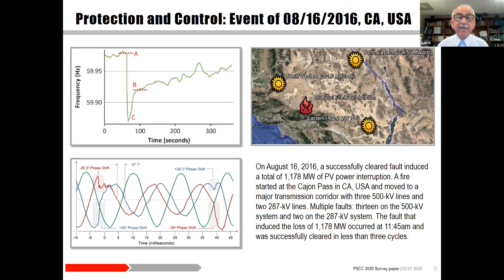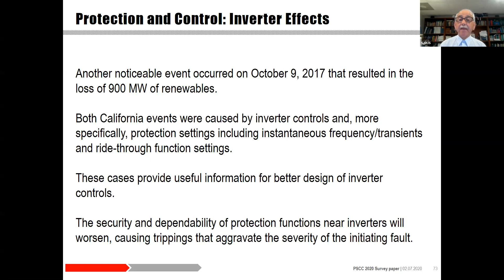basically the same procedure. We lost generation because of the interaction of the controls and the protection of the inverters in the renewables. In this particular event, we lost about 900 megawatts. Now, the study of these cases provides useful information for better design of inverter controls, but we also have to realize that to deal with these problems, the inverter controls have to become much more complex, and complexity brings more problems. Okay.